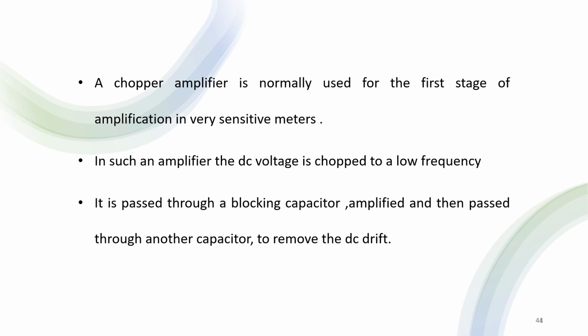The chopper eliminates the need for a high gain DC amplifier with its inherent drift and stability problems. The input impedance of a chopper amplifier DC voltmeter is usually of the order of 10 megaohms or higher except in low input ranges. So, in order to eliminate the errors caused by high source impedance, an arrangement for nulling is included in the meter circuit. A control facility is provided on the front panel of the instrument which permits the input voltage to be nullified with the bucking voltage. When the bucking voltage is equal to the input voltage, the null is indicated, the meter exhibits infinite impedance and therefore the loading effects are totally eliminated. The input voltage is then removed and the bucking voltage equal to the input voltage is indicated by the meter.